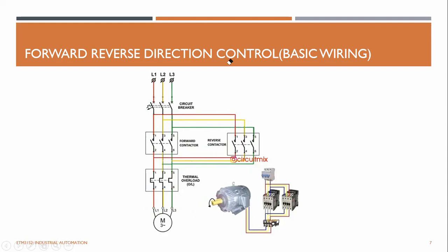And interestingly, you can't press the forward and reverse contacts at the same time. It will damage the motor, right? So there should be some kind of interlocking. If this forward contact is pressed, we should not allow the reverse contact to be operated by someone else. If the reverse contact is operated, the forward contact should be open and should not be allowed to operate. Okay, so interlocking should be there. Otherwise, if someone presses both these contacts, it will be really damaging.